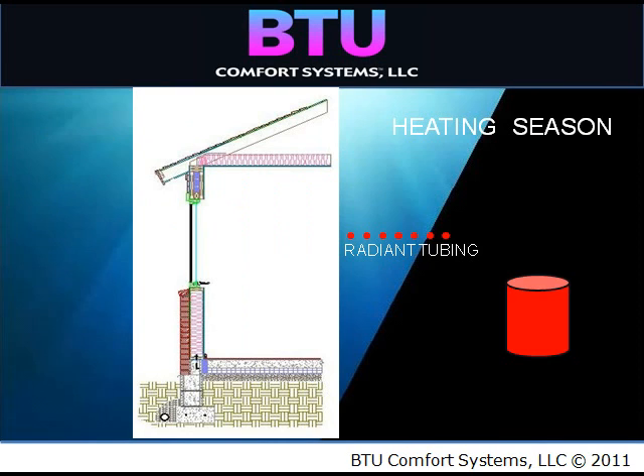In the heating season, there are a couple choices for heating. Use the floor or the ceiling. Let's take a look at the floor process. The heated fluid travels through the tubing embedded in concrete. This entire surface mass heats to an ideal temperature somewhere between 76 and 86 degrees at the surface to maintain a comfortable interior space. Heat radiates to cooler objects, heating them. Heat goes to cold, seeking an equilibrium of temperatures. Because of the large amount of mass, rapid changes to temperature settings are not feasible. Typically, it takes between 4 to 8 hours for a change in a thermostat setting to take effect.